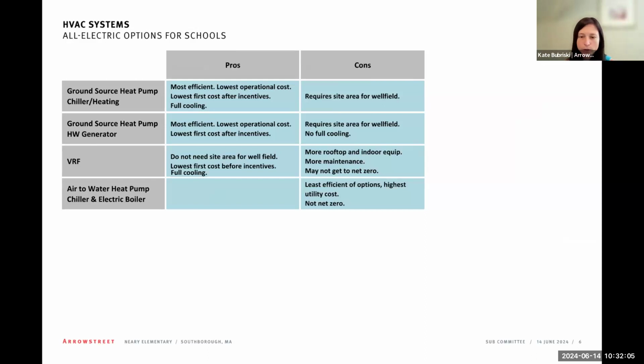You obviously need a well-field area, and so that is a consideration. Option 2 is very similar, except it doesn't have the full cooling. And then the VRF system: the main advantage there is there's no well field required. It will be the lowest first cost before any incentives. It can maintain full cooling. It may not get to net zero, so that's really the biggest con.